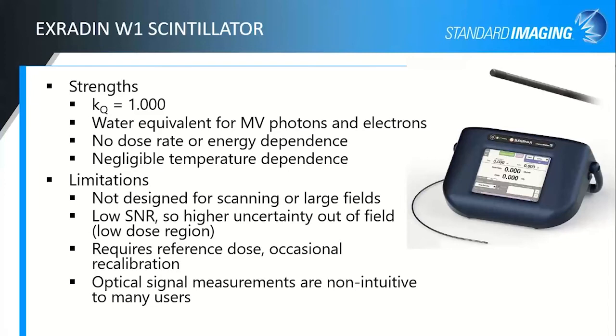The W1 has a low SNR, so there's a higher uncertainty in the dose out of field. If you were trying to do a point-by-point measurement of a field profile, you'll get a higher uncertainty for those out-of-field measurements. You will start bumping up against the electronic noise floor of the system.